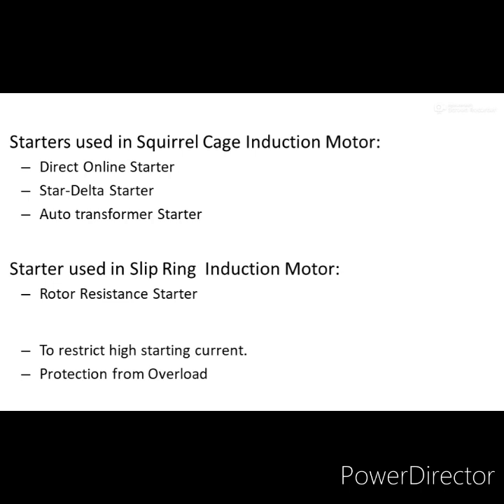In a slip ring induction motor, the circuit used is the rotor resistance starter. We use a starter circuit in order to restrict the high starting current. The initial current when we provide supply to the motor is very, very high. In order to restrict that initial current, we use a starter circuit so that the windings of the motor can be protected. There is also a provision to protect the motor from overload conditions.